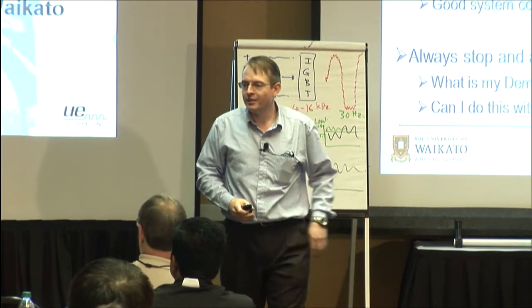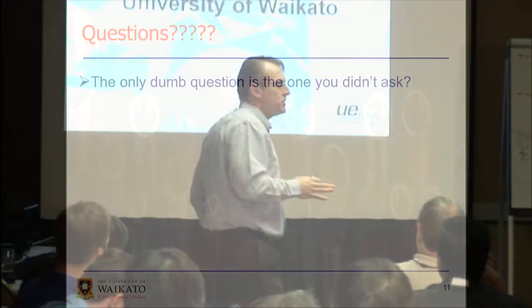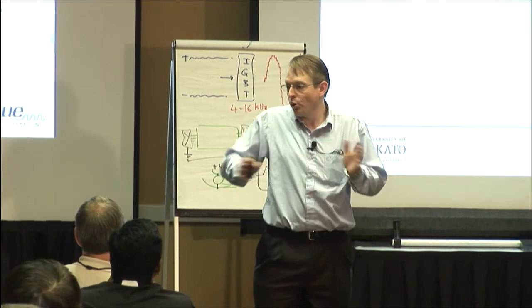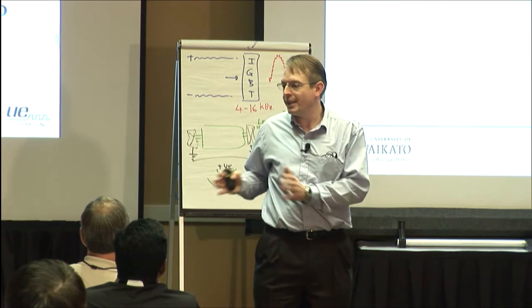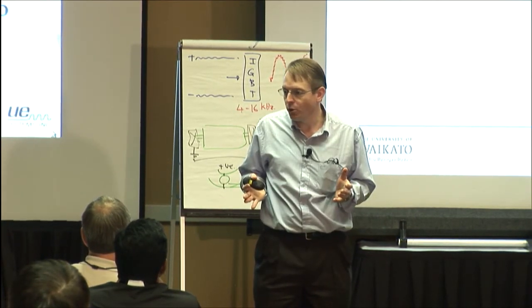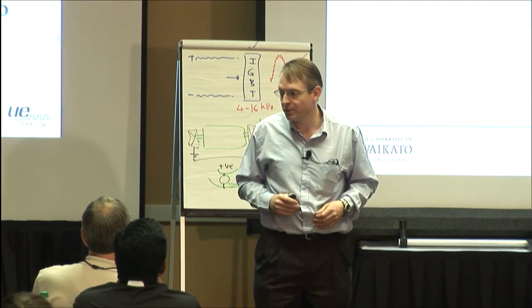Yeah? What is the relation between the torque and the speed? Well, very good question, and this is one of the special reasons why you might want to use a VSD, because one of the advantages of a VSD is you can generate whatever torque you need at whatever speed you need it at. Whereas with a motor run direct online, your torque's a direct function of the slip based on load and speed and all the rest of it.